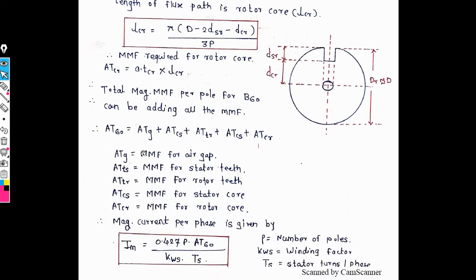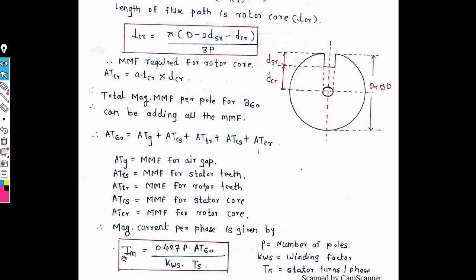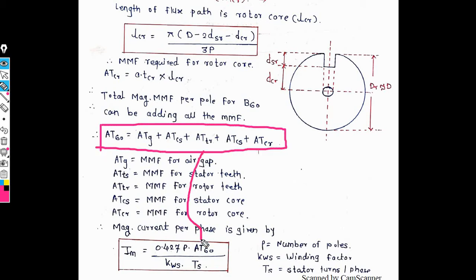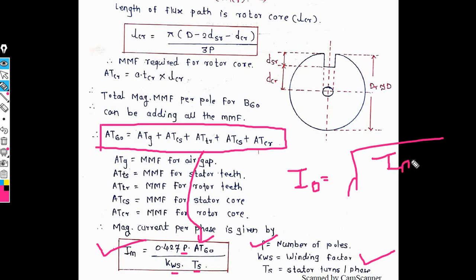The formula for magnetizing current per phase in a three-phase induction motor is: Im = 0.427 × P × AT₆₀ / (Kw × Ts), where P means number of poles, AT₆₀ means ampere turns at 60 degrees, Kw means winding factor, and Ts means stator turns per phase. This is the magnetizing current for three-phase induction motor. The second parameter remaining is the core loss component. No-load current I₀ equals the square root of Im² plus IL².